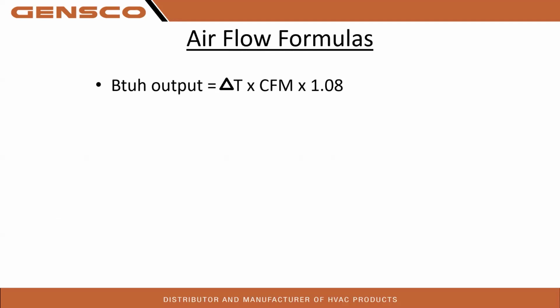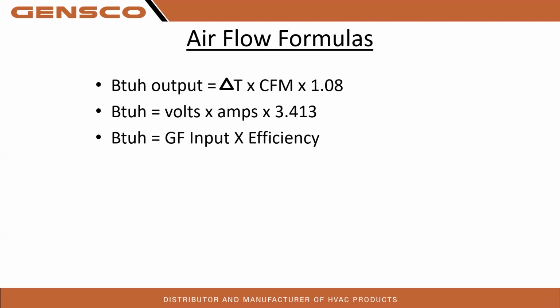So that's another good analogy to tell your homeowners to increase their return air. So, airflow formulas, this is a great one. You can write these down. You can text this in. We have forms for you, some startup sheets with these formulas on there. This does come in handy when you're in the field. So BTU output is your delta T, which is your supply air minus your return air, times your CFM times 1.08. 1.08 is an altitude factor. In the gas furnaces, they do have the altitude correction factors. I think 1.08 is good to 2,000 feet elevation. So your BTU equals volts times amps times 3.413. BTU equals gas furnace input times efficiency, which we can find on the data plate.